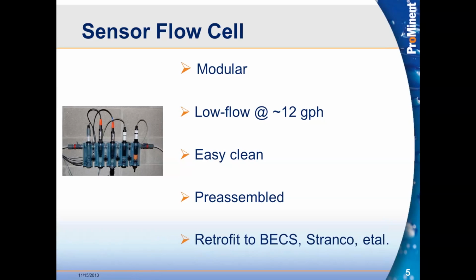Other manufacturers don't have this fabulous design for their flow cells, and so what they wind up doing is having all these adjunct or add-on flow cell assemblies with pressure gauges and extra booster pumps and special assemblies for maintaining proper pressure and volume through the cell, where our cell, by design, by engineering, does that within its form. It's easy to clean. If you ever get some sand blow through out of a sand filter into the flow cell, you can just undo the modules and easily rinse these out. There are small cleaning ports on the bottom that really facilitate the rinsing nicely.